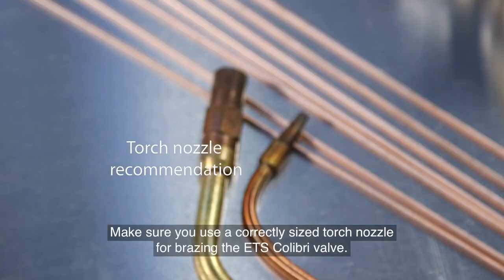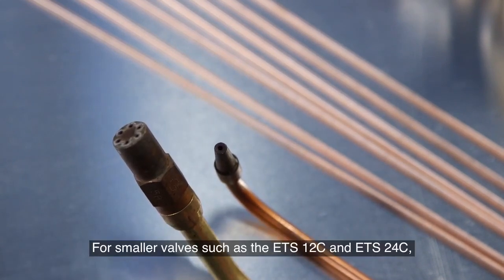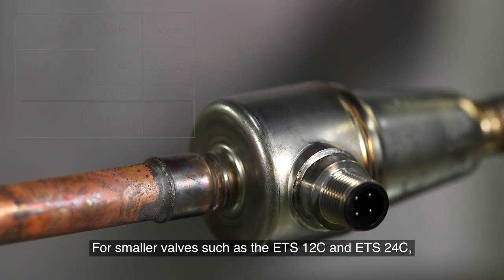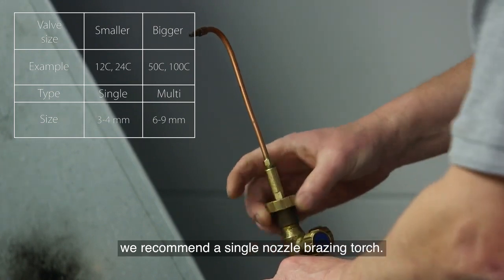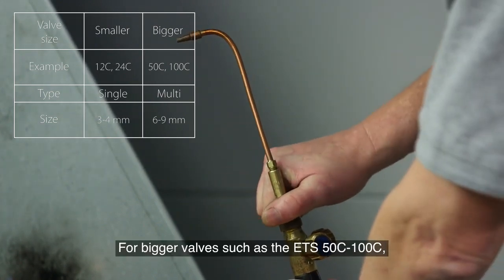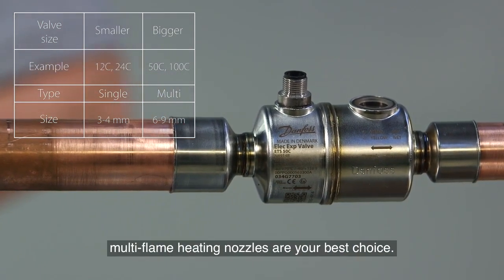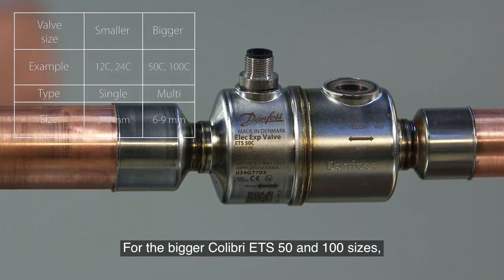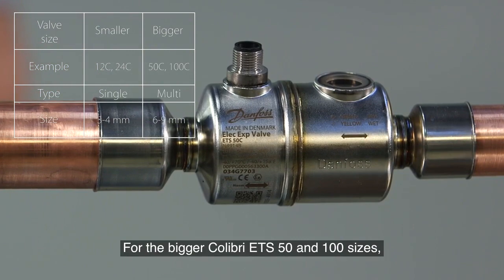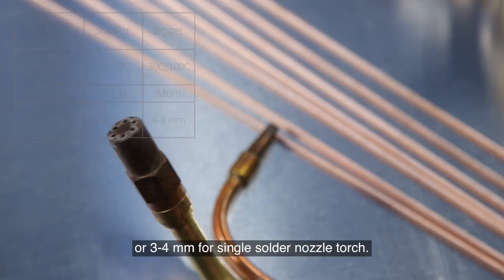Make sure you use a correctly sized torch nozzle for brazing the ETS Colibri valve. For smaller valves such as the ETS 12C and ETS 24C, we recommend a single nozzle brazing torch. For bigger valves such as the ETS 50C to 100C, multi-flame heating nozzles are your best choice. For the bigger Colibri ETS 50 and 100C sizes, we recommend a 6–9mm solder nozzle or a 3–4mm for single solder nozzle torch.